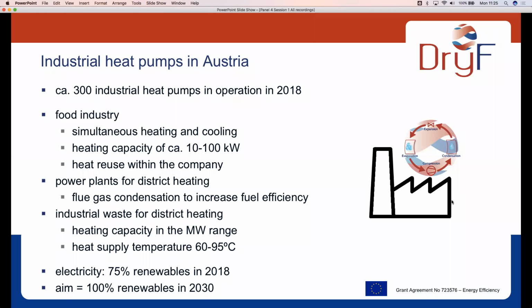Okay, perfect. So in Austria, industrial heat pumps are gaining more and more importance, and there's a statistic that is published every year where they also count the number of industrial heat pumps that are in operation. So far, there are about 300 installations. There are three main areas of application where we find those heat pumps. The most important one is the food industry. There, heat pumps are used for heating and cooling, and those installations usually have a capacity of several 10 to 100 kilowatt, and the heat that is supplied by the heat pump is usually reused within the company. So it's either used for space heating to heat the production halls or for process heat.